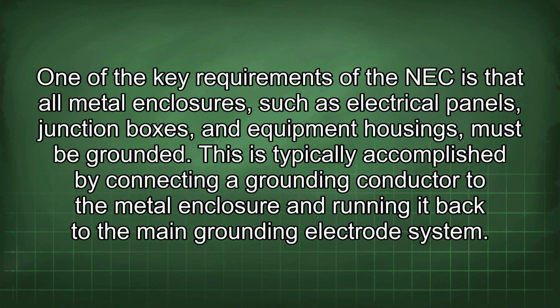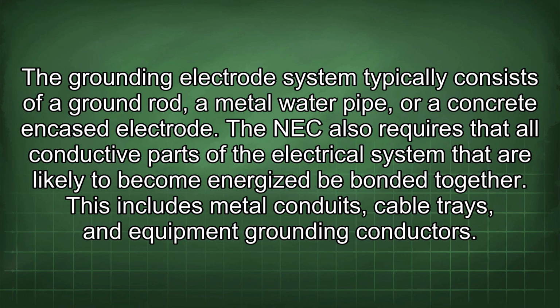One of the key requirements of the NEC is that all metal enclosures, such as electrical panels, junction boxes, and equipment housings, must be grounded. This is typically accomplished by connecting a grounding conductor to the metal enclosure and running it back to the main grounding electrode system. The grounding electrode system typically consists of a ground rod, a metal water pipe, or a concrete encased electrode.